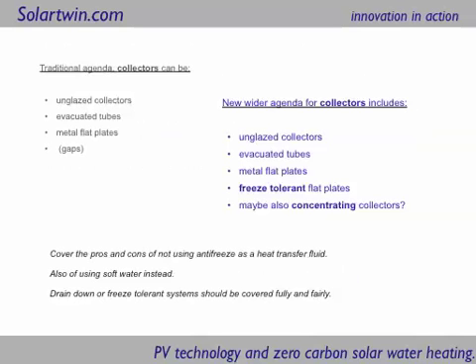They are solar collectors that can freeze solid without cracking, and if you type in Solar McGregor on the web you'll see some other videos about that. The benefits of not using antifreeze are that you can replace it with water, and water is six times less sticky. Six times less sticky means six times less power use for your pump, and we'll see in a moment that this is really important.